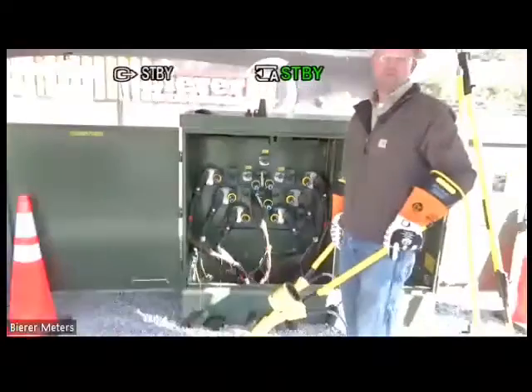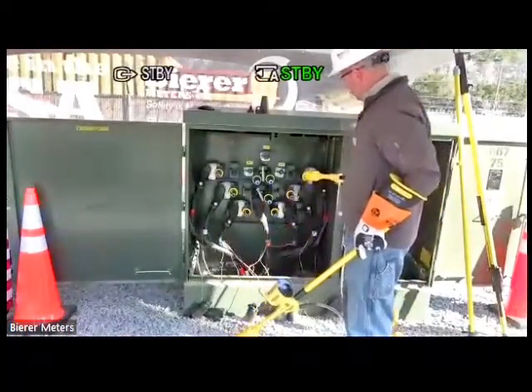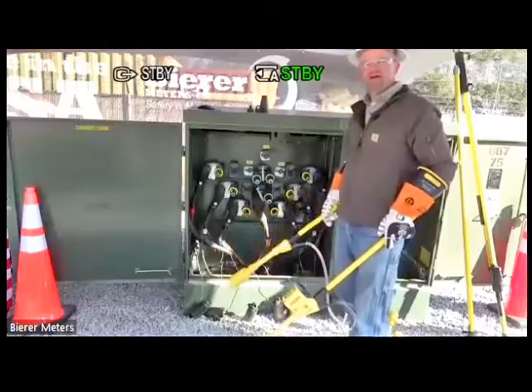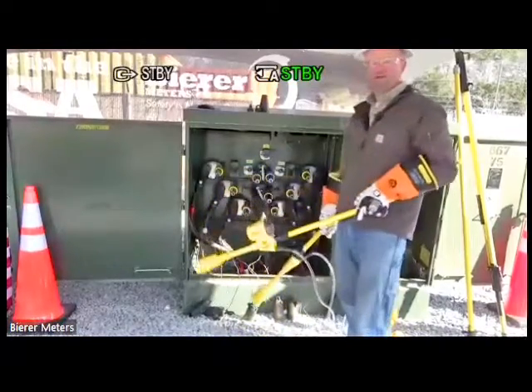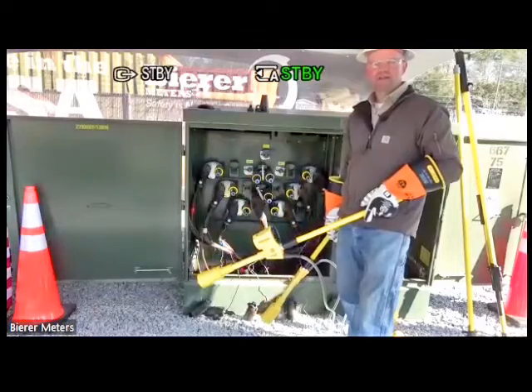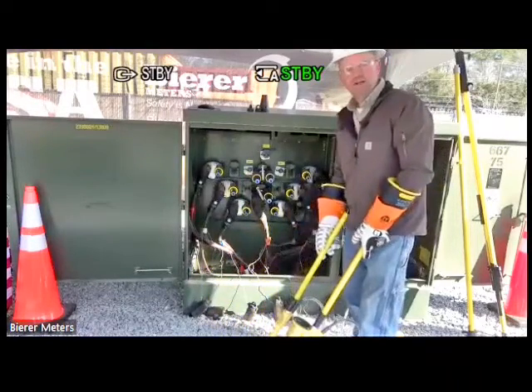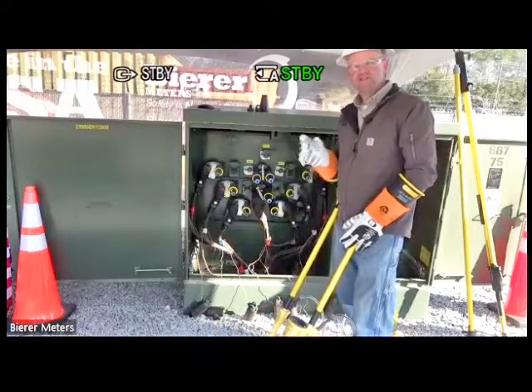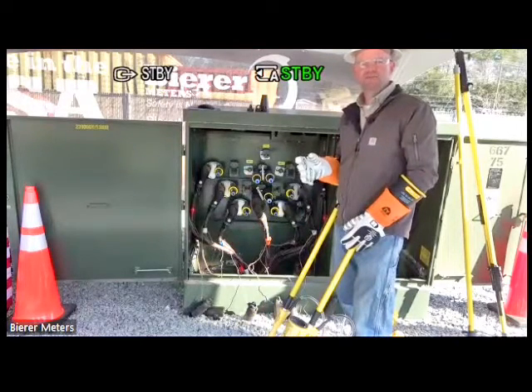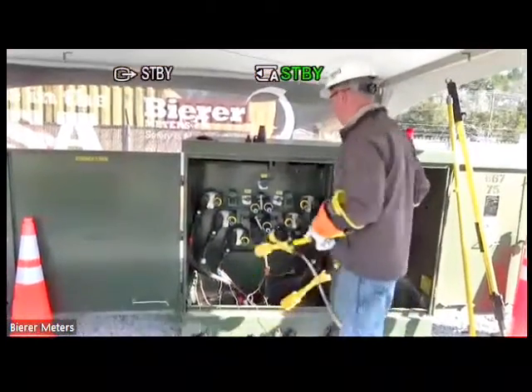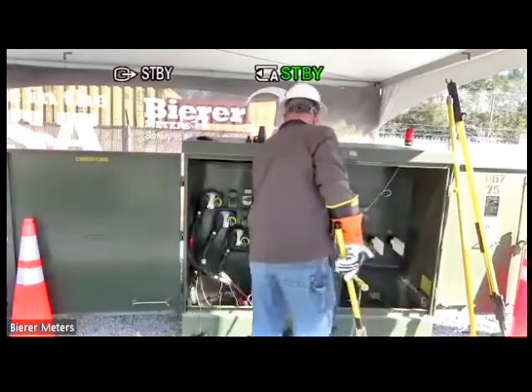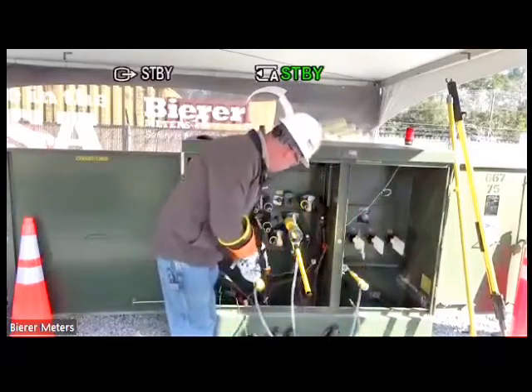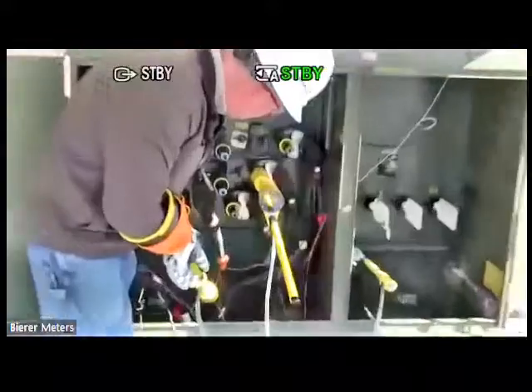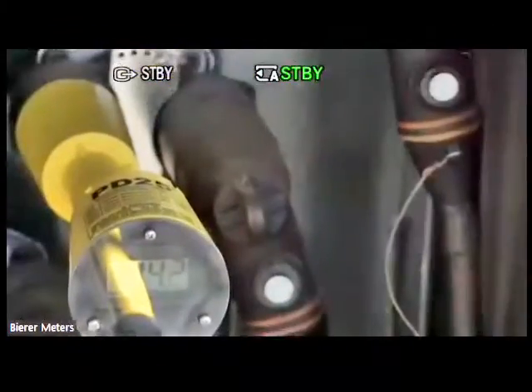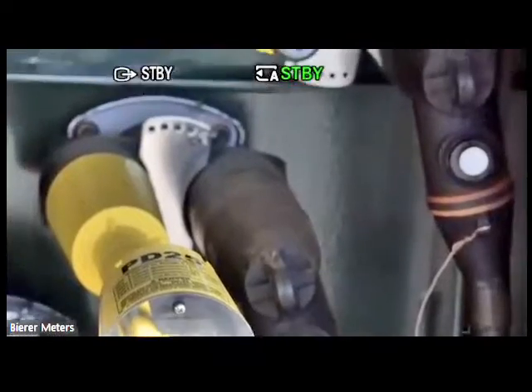14,100, okay? Now, notice I'm going to do this a little bit different here. I actually went using my second probe phase to ground. I'm going to go my meter probe with my second probe to ground. That may not sound like a big deal, but again, other manufacturers, you'll actually see a discrepancy in that reading. It won't be the same. So I'm just going to prove real quick that if I did go to the same phase, phase to ground this way, there's my 14,100. Roll over to 200 a little bit. So again, within 100 volts, within 1%.